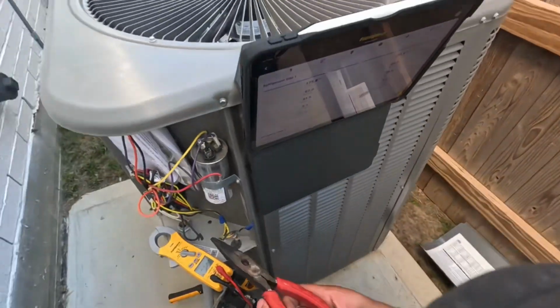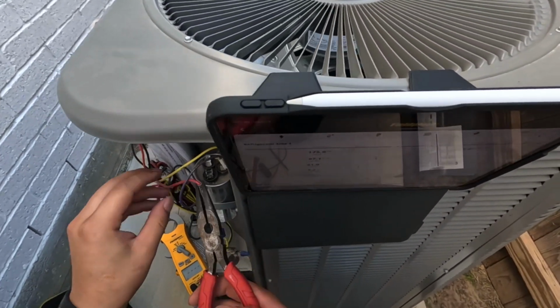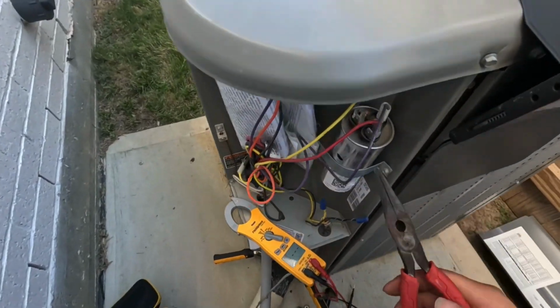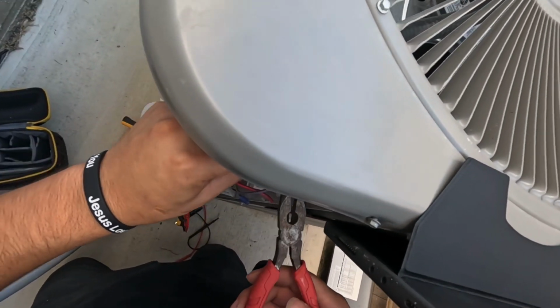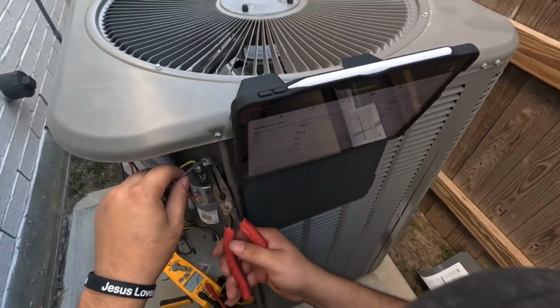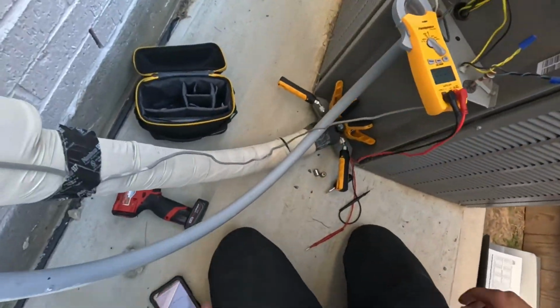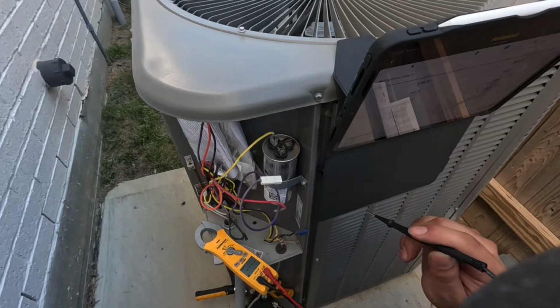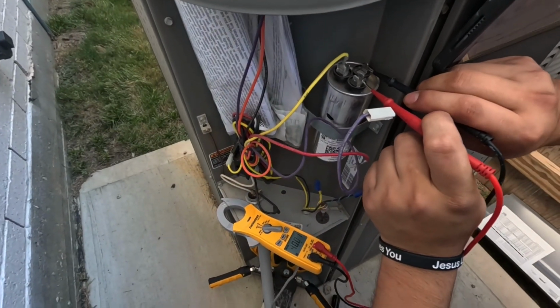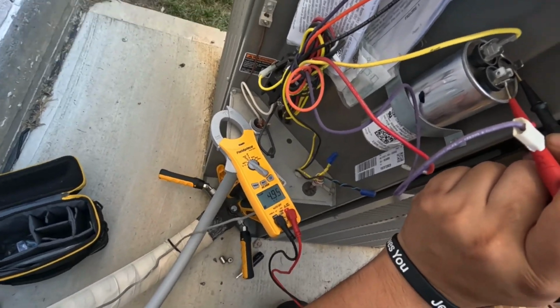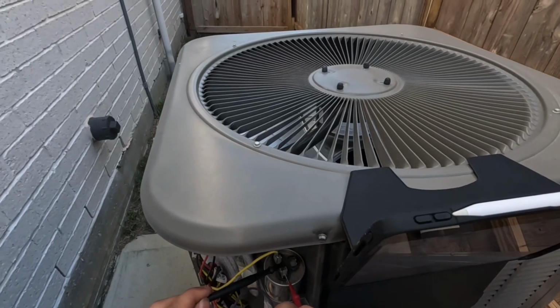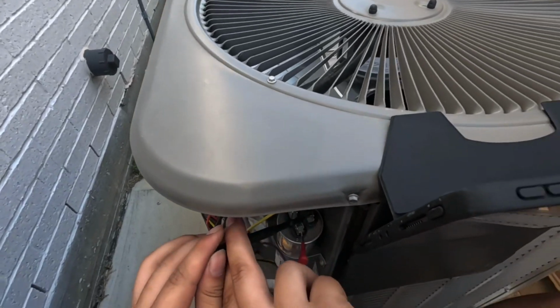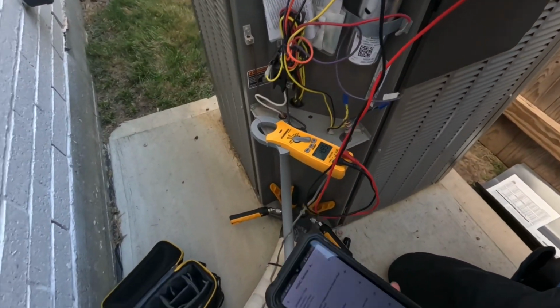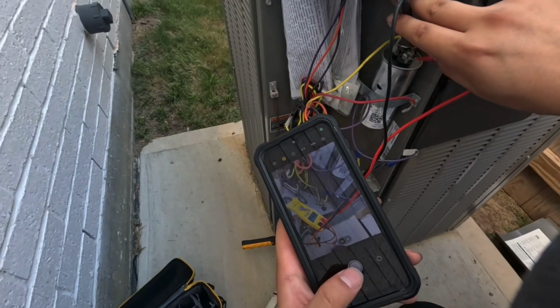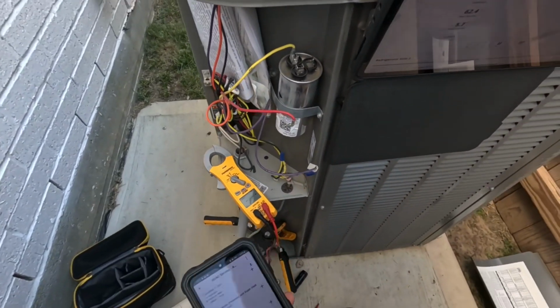Okay, so this capacitor has charge in it, so you don't ever want to touch the contacts with your hands. So notice this common just stays off. So whenever you check a capacitor, you want to check common to fan or common to compressor. You do not want to check the compressor to fan because that's not the way to do it. So common, fan, supposed to be 5. 4.9 is pretty decent. I mean, it's still good. Put that one right here. Okay.